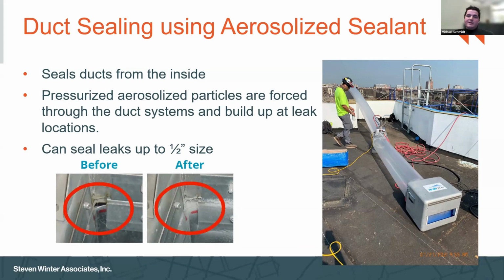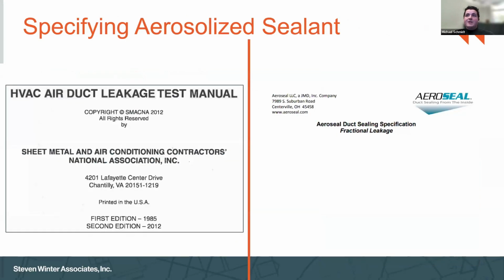So you'll see that before and after shot. Typically, this can seal about a half an inch. So it's still important that good hand sealing practices are used, but it can be a very effective strategy. Essentially, we've seen down to 1% or less than 1%. For example, at Cornell Tech, they were less than 1% duct leakage on that project, which is very impressive, and just a testament that this can be done using good practices.